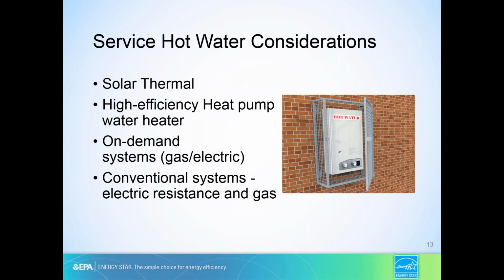And what this does is it uses heat pump technology, and it actually has about a half a ton or 3/4 of a ton of cooling. So it will actually cool a space like a heat pump or an air conditioner would. And then the output of that process is the heat. And instead of rejecting that heat outside like a condensing unit, it rejects the heat to a storage tank to make hot water. So it's a good win-win process for cooling a space, whether it's a small garage or a semi-unoccupied space, or even in a mechanical room that vents to an occupied space. It's going to provide a little bit more cooling, and it's going to provide heating for that building.